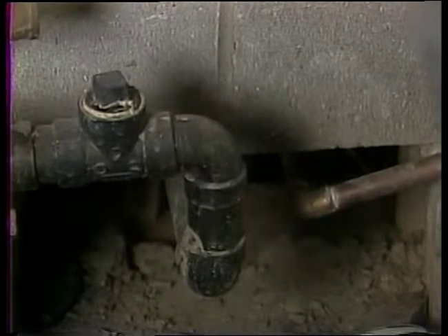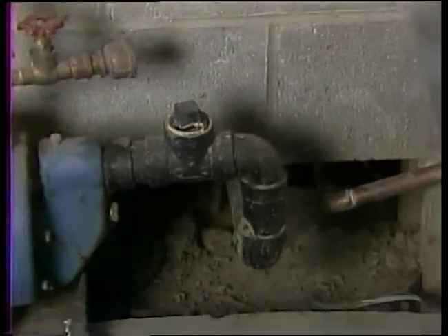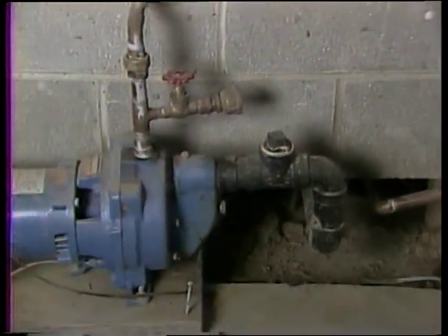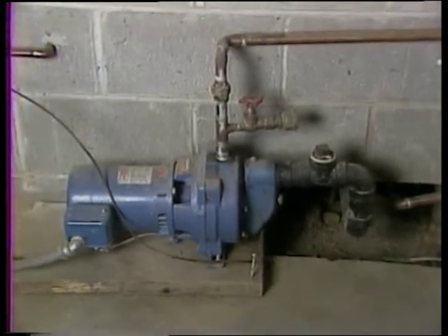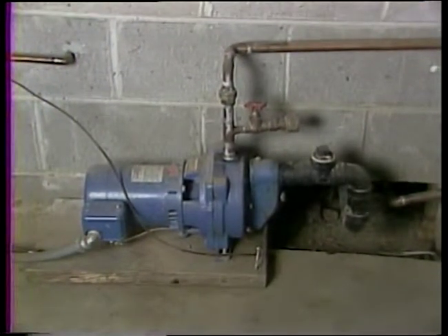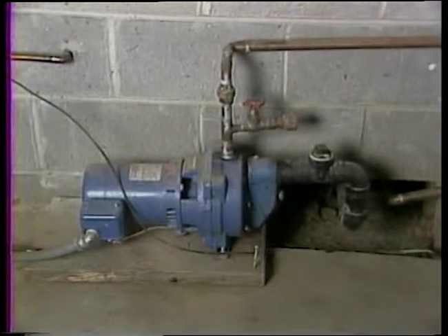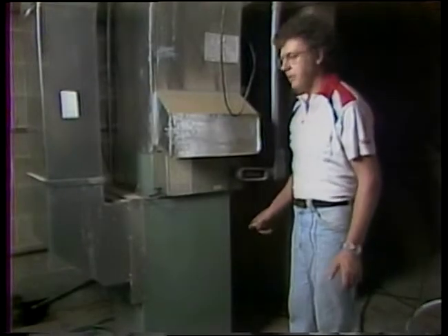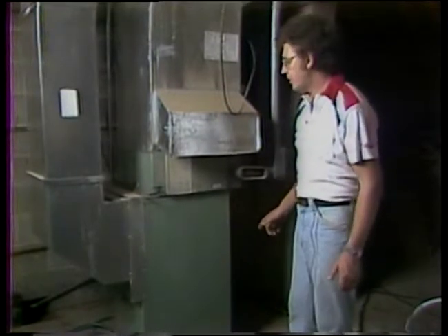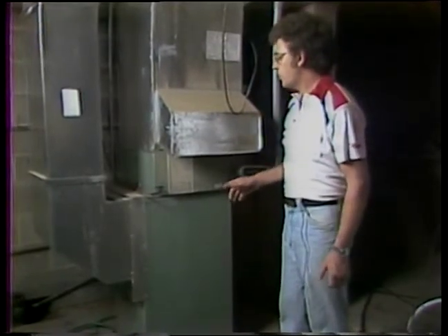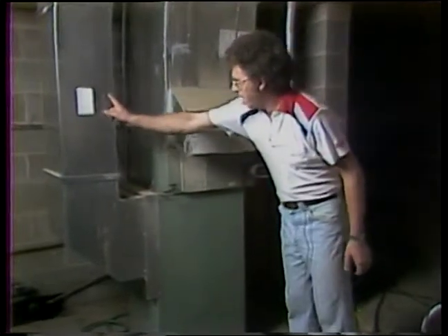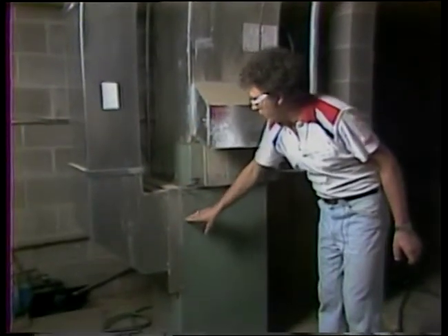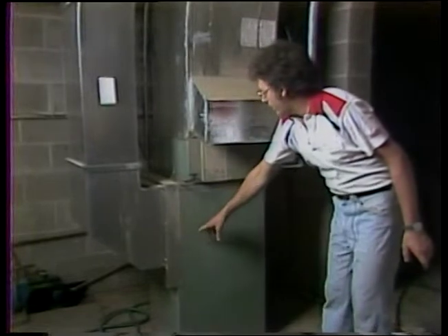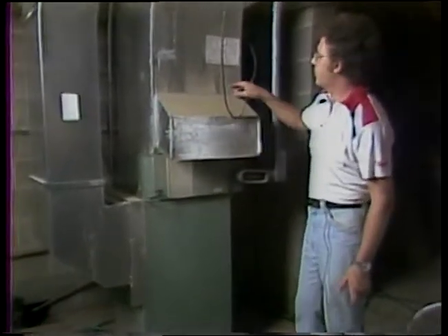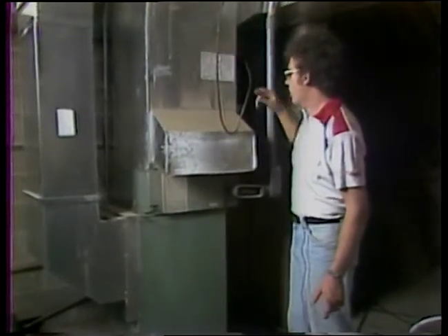This is the pump that is used to pull the water out of the storage tank and pump it through the heat pump. It's a conventional centrifugal type pump, and we pump it through the heat pump at about 6 to 8 gallons per minute. This is the heat pump, which is really the heart of the solar-assisted system. It's a Carrier water-to-air source heat pump. The return air from the house comes down this duct through a heat exchanger, which is in this particular area, through a blower and back up to the house via the standard ductwork.